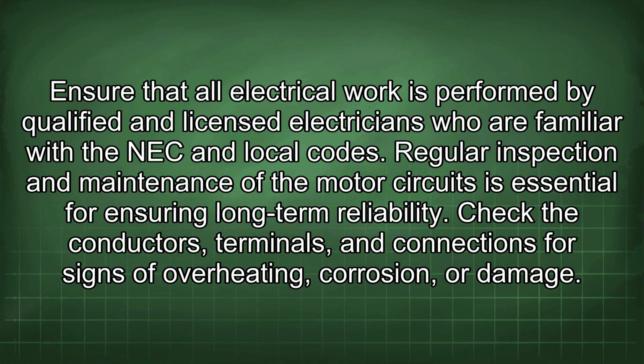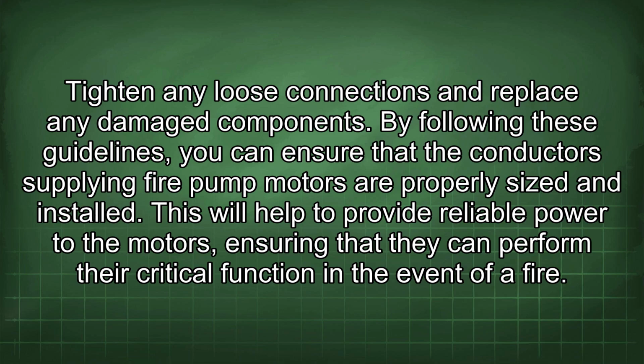Ensure that all electrical work is performed by qualified and licensed electricians who are familiar with the NEC and local codes. Regular inspection and maintenance of the motor circuits is essential for ensuring long-term reliability. Check the conductor's terminals and connections for signs of overheating, corrosion, or damage. Tighten any loose connections and replace any damaged components. By following these guidelines, you can ensure that the conductors supplying fire pump motors are properly sized and installed.